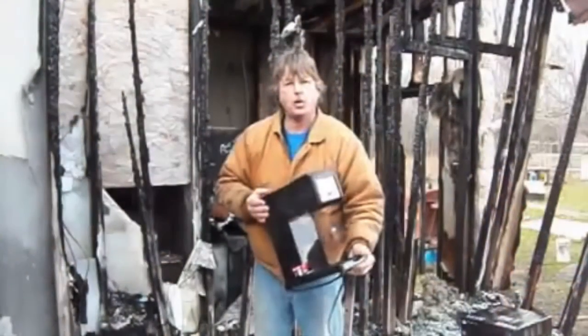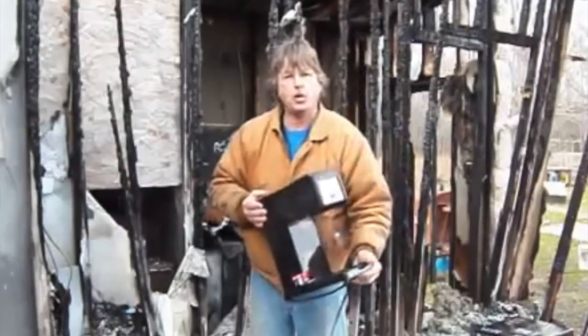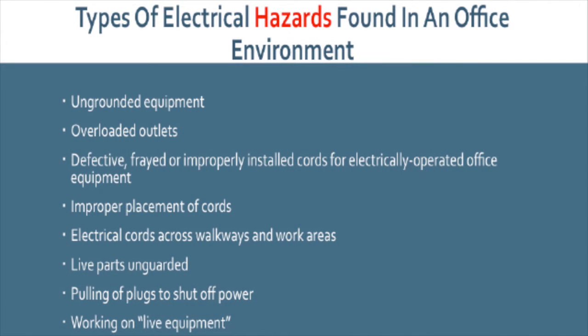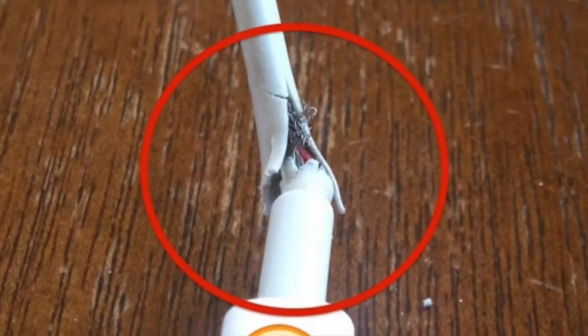When the outer jacket of a cord is damaged, the cord may no longer be water resistant and the insulation can absorb moisture, which may then result in a short circuit or excessive current leakage to ground. If wires are exposed, they may cause a shock to a worker who contacts them. These cords should be destroyed and replaced. Electric cords should be examined on a routine basis for fraying and exposed wiring.